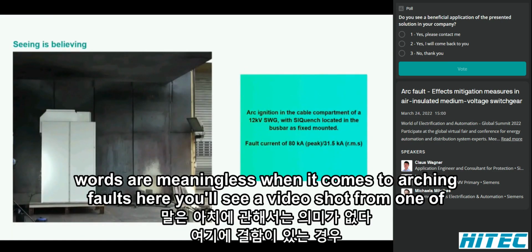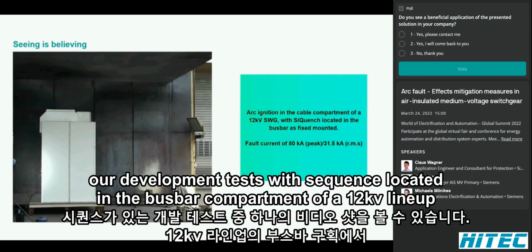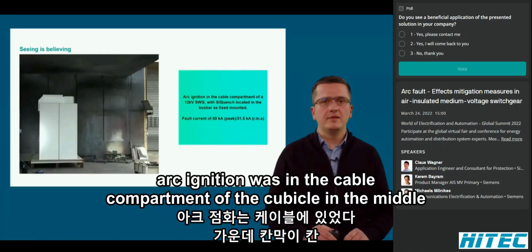Words are meaningless when it comes to arcing faults. Here you'll see a video shot from one of our development tests with SIQuench located in the busbar compartment of a 12 kV lineup. Arc ignition was in the cable compartment of the cubicle in the middle.